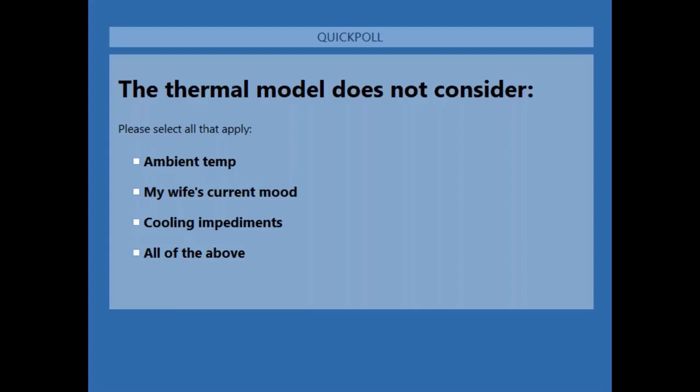a reminder that the thermal model is just that. It is a model. And unfortunately, it has its limitations. It does a reasonably good job of computing what we call the TCU, the thermal capacity used. Just so you know, GE Multilin invented this technology. There is a patent on it. I'm fairly certain that patent has now expired, but this was conceived by the folks at Multilin before it was purchased by GE. But it has its limitations.